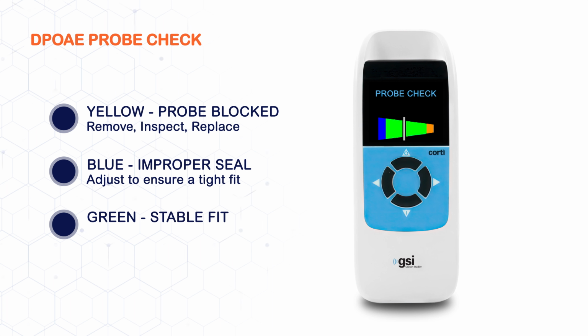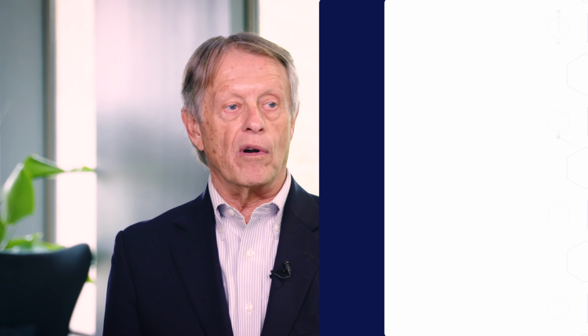When the white marker is in the middle of the cone and a stable fit is detected, testing will begin automatically. During testing, you will see some bars appear on the display screen of the DPOAE device. These are the results for each test frequency. The device automatically analyzes the child's DPOAEs and determines whether the screening result is a pass or a refer.